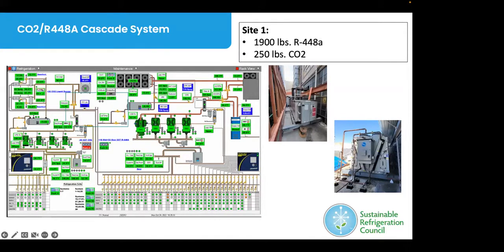The system served both medium temp and low temp with 1,495 pounds of R407A with an evaporative condenser cooler. We came in and replaced that with a cascaded system with R-448A over CO2.